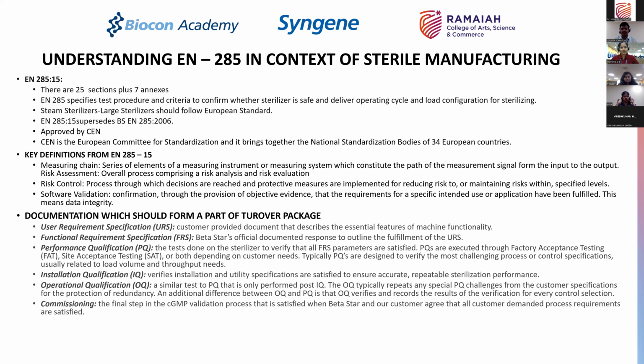Okay, so generally in a sterile manufacturing operation, there is also a sequence in which you can do a qualification. If your pure steam was not qualified, you cannot use it for the autoclave cycle development, for example, because your steam itself is not qualified. If your air is not qualified, then you cannot use it.